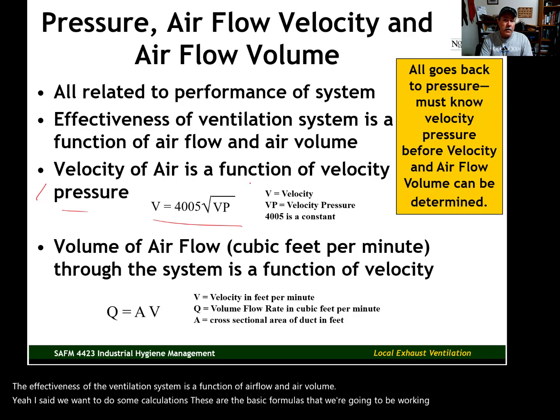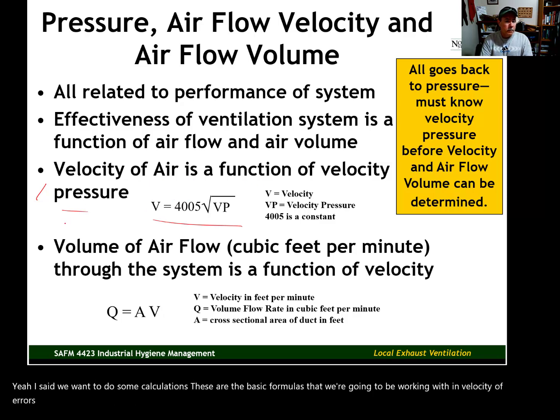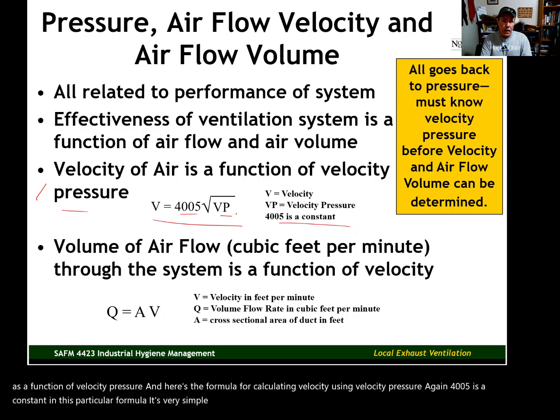Velocity of air is a function of velocity pressure. And here's the formula for calculating velocity using velocity pressure. 4005 is a constant in this particular formula. It's a very simple formula once we know velocity pressure.